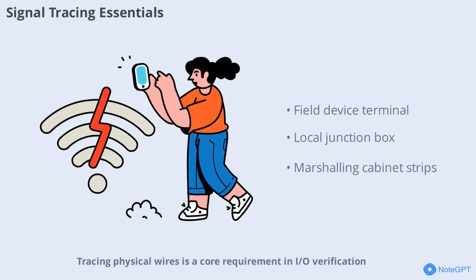Tracing physical wires is a core requirement in I/O verification. The guide outlines the path you must follow, from the field device terminal to the local junction box, to the marshalling cabinet terminal strips, to the S800 I/O module terminal base, and finally to the software channel in CBM. This thorough tracing ensures that every connection is correct and that signals flow as intended from field to control system.